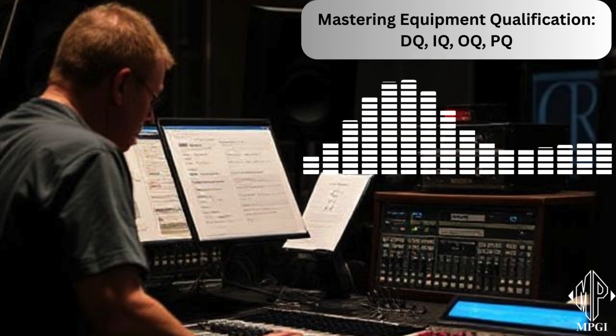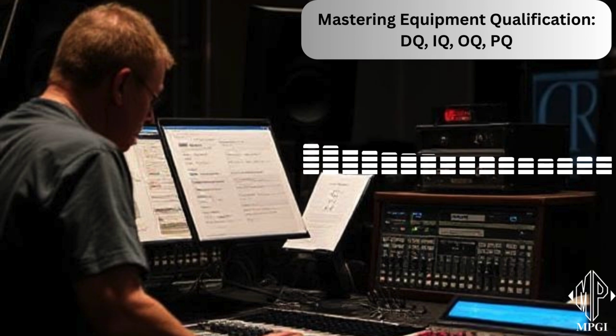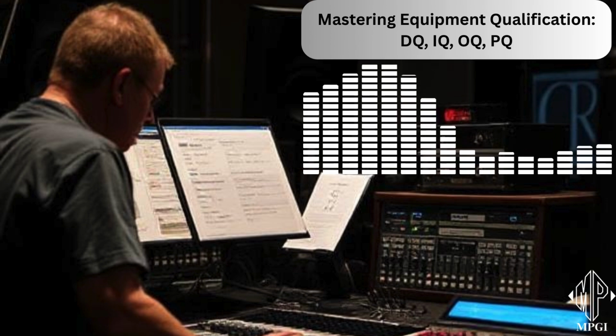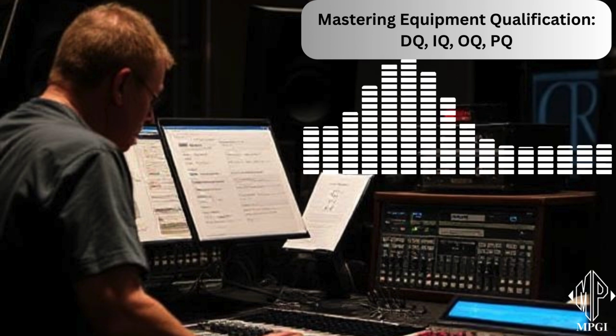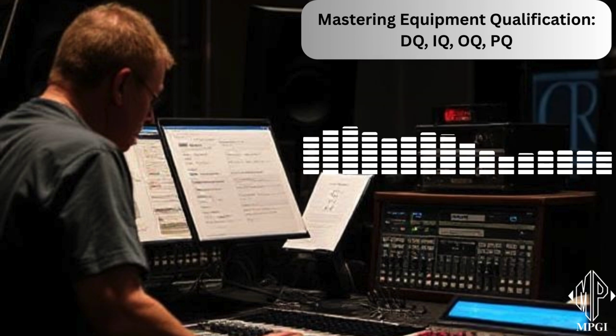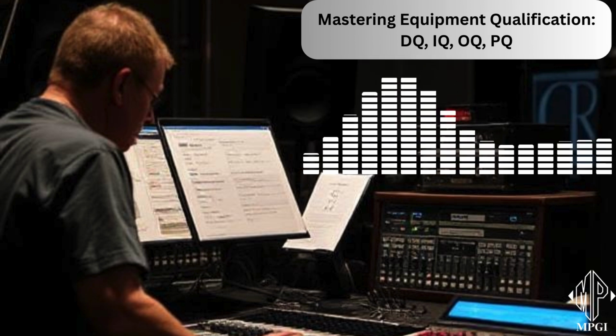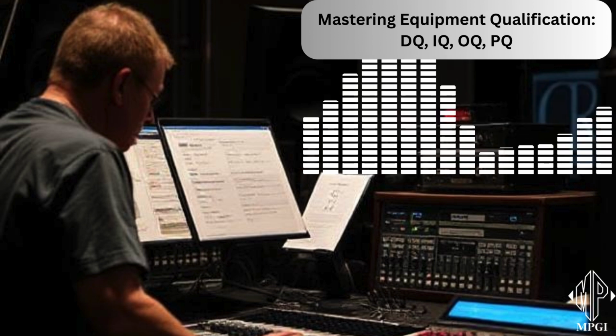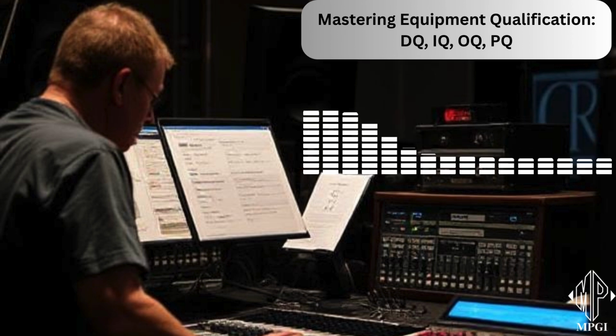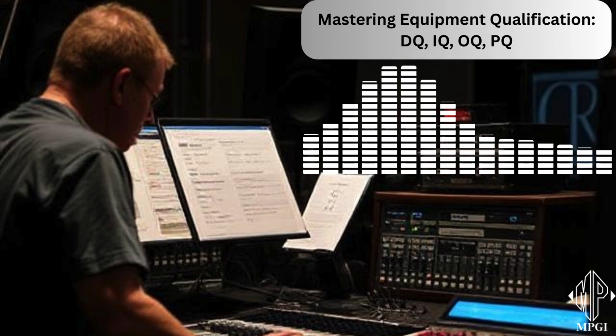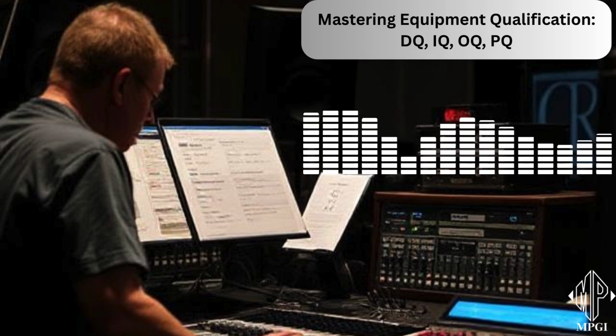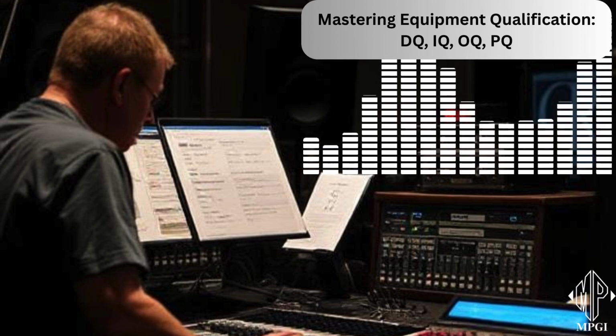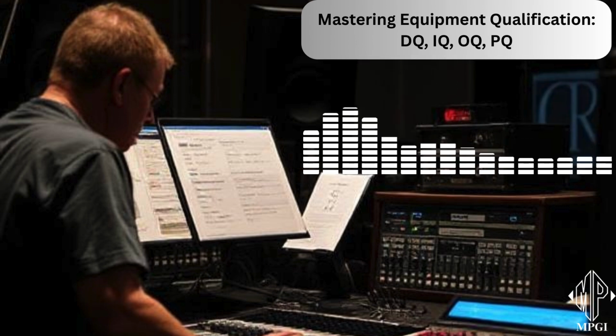So what do the regulations say about this operational qualification phase? Well, 21 CFR Part 211.67 for pharmaceuticals specifically mandates proper cleaning, maintenance, and sanitization or sterilization of equipment within its operating parameters. That's on ecfr.gov. So OQ basically proves that the equipment can be consistently cleaned and sterilized effectively. Right. Then there's 21 CFR Part 211.68, which requires regular calibration, inspection, and checking of all those automated mechanical and electronic systems. All things that are carefully checked during OQ.